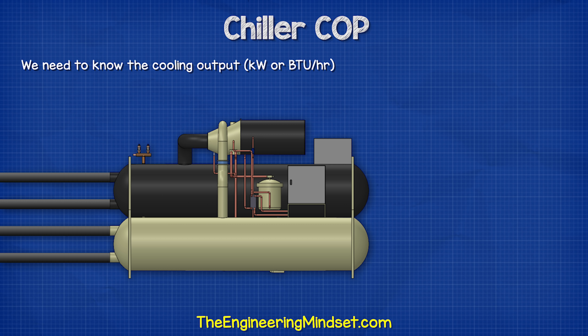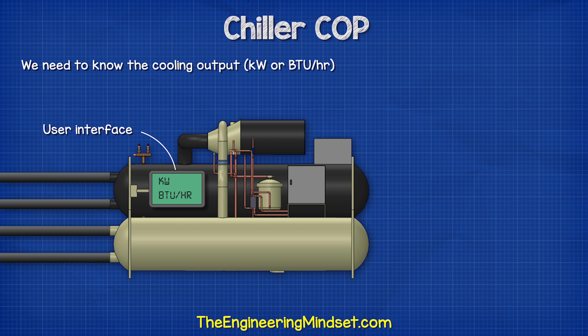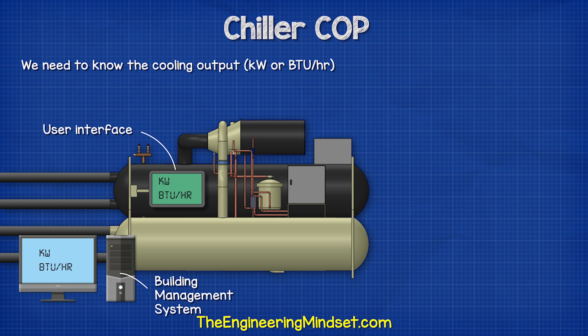The second part you will need to know is how much cooling you are getting out of the chiller evaporator. Ideally, this will also be in kilowatts, which makes it much easier, but you can also use BTUs for the imperial calculation as we'll simply convert this. This value should also be available from the chiller's user interface or from the building management system.